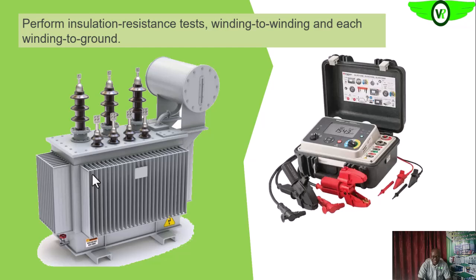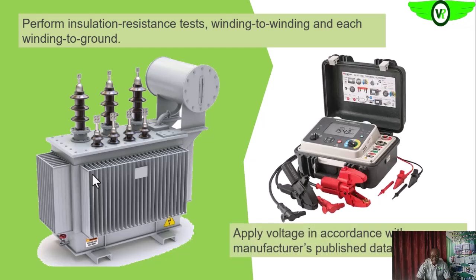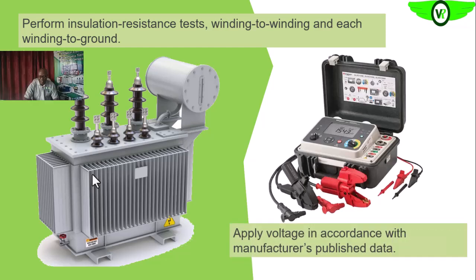So we also do insulation resistance test. You can check the description below for a link to insulation resistance test training if you are not too familiar with it. So we'll do the insulation between phases, and then between the windings and the ground. If the unit is connected inside, delta inside and star inside, of course what we'll be measuring is between the windings and the ground. So that is what we'll be looking at at the end of the day. So we want to ascertain that the insulation of the transformer is as required.